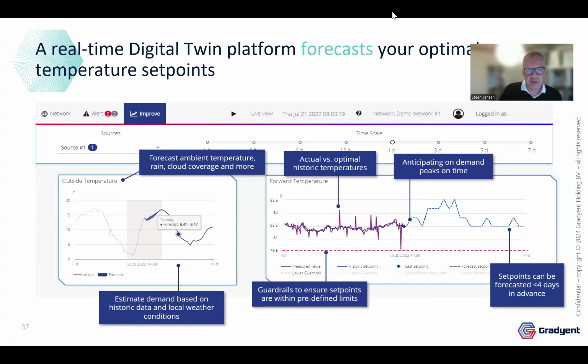We would typically do set points like you see here. The blue curve is the set point predicted by the digital twin. The dotted line shows how we suggest the set point some days ahead, and the purple line is the actual temperature. Here they follow actually quite closely. Sometimes clients use it as a recommendation and then adjust the settings themselves, but in many cases district heating companies want to go into kind of autopilot, where we just write the set points to the SCADA system and it runs more or less automatically.